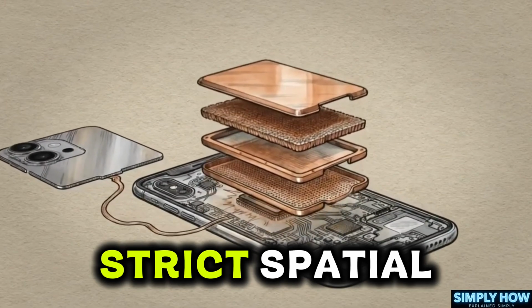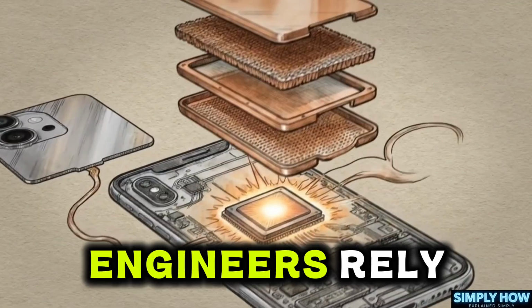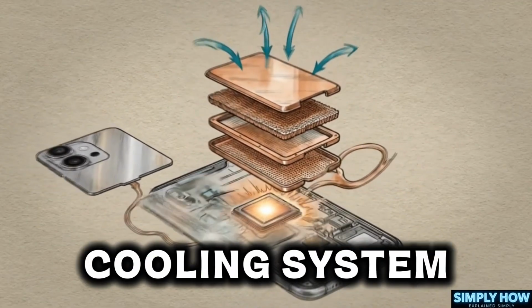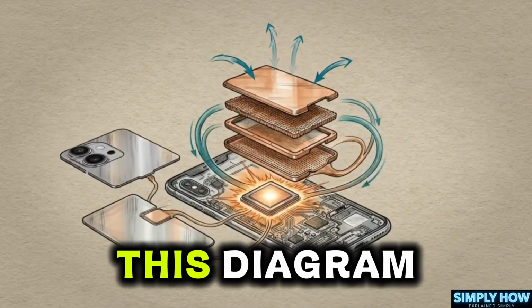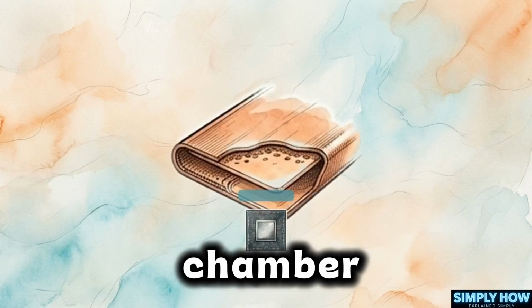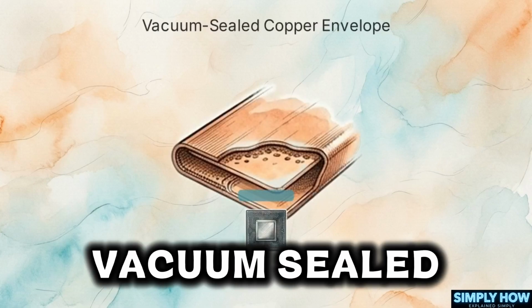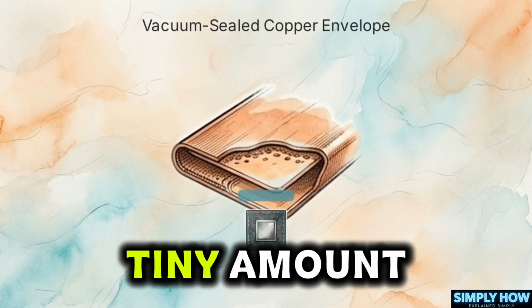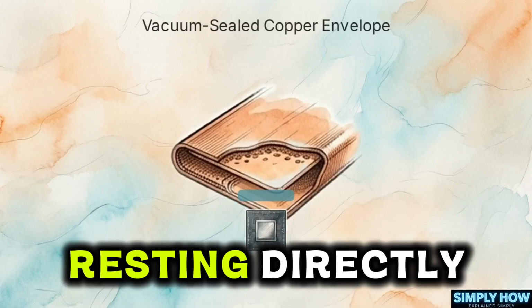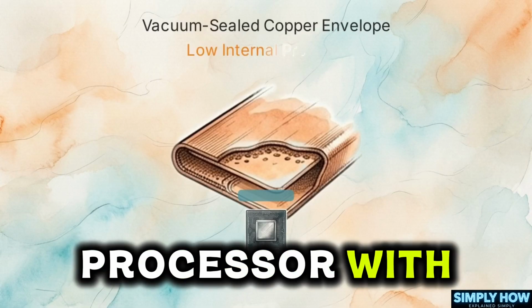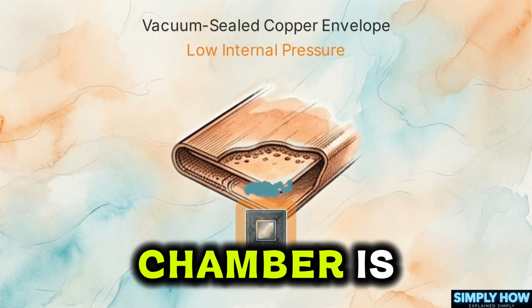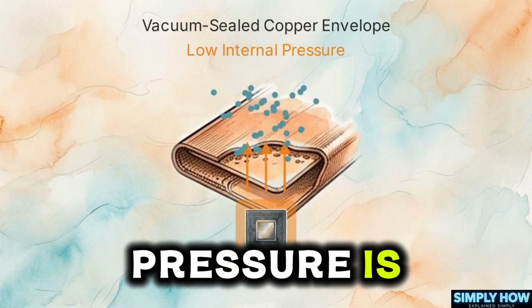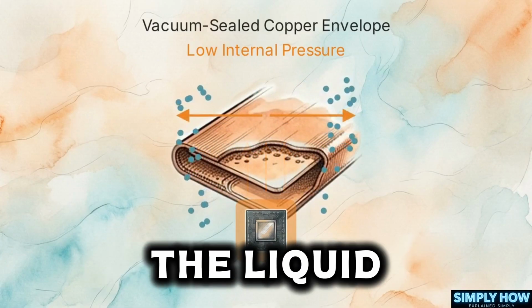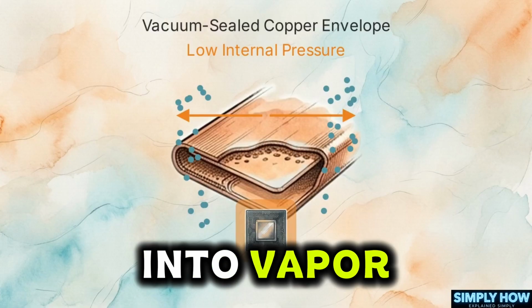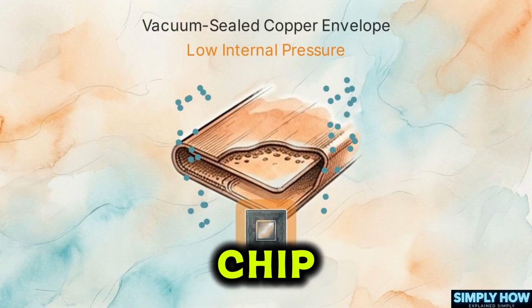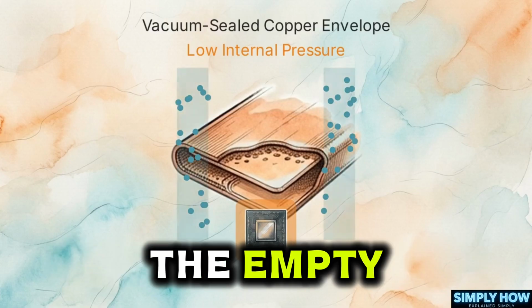To get around this strict spatial constraint, engineers rely on a passive liquid cooling system called a vapor chamber. This diagram reveals the inside of a vapor chamber. It is a flat, vacuum-sealed copper envelope containing a tiny amount of liquid coolant resting directly above the processor, with empty space above it. Because the chamber is a vacuum, the internal pressure is incredibly low. This allows the liquid to boil and flash into vapor the instant it touches the heat from the chip, rapidly rushing outward through the empty space.